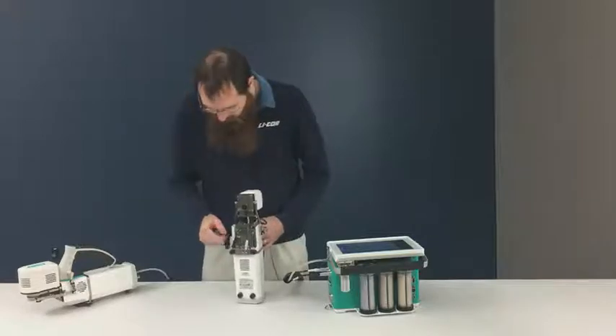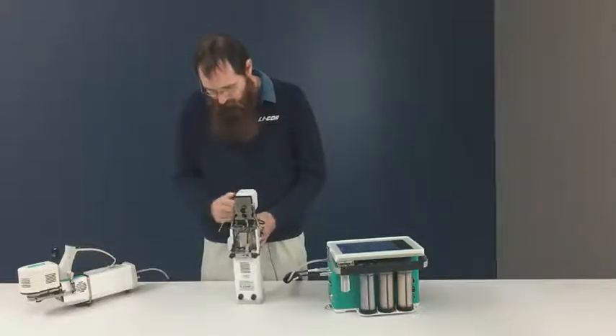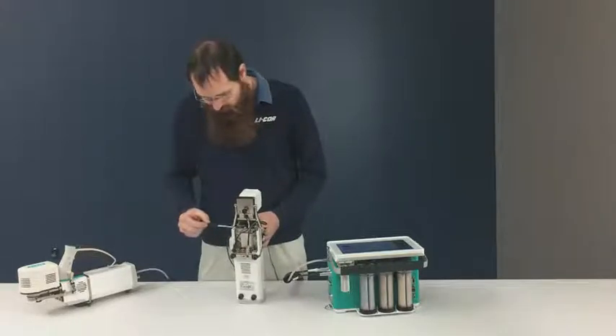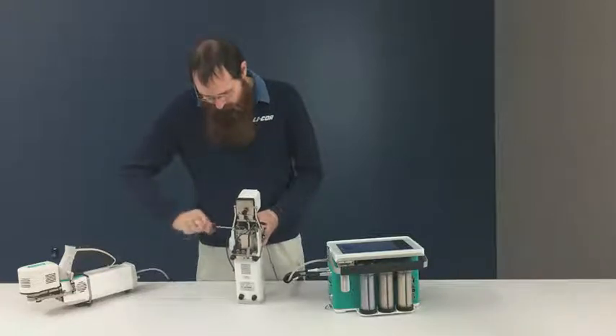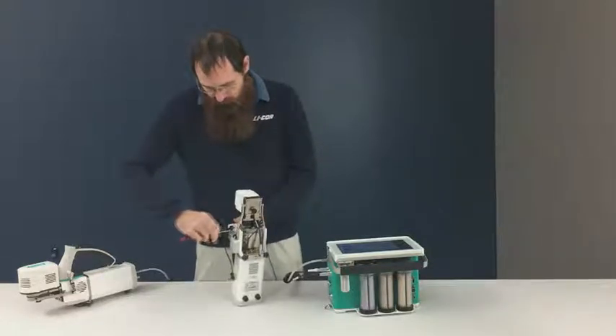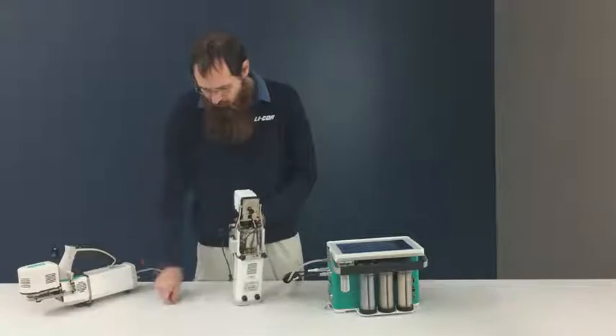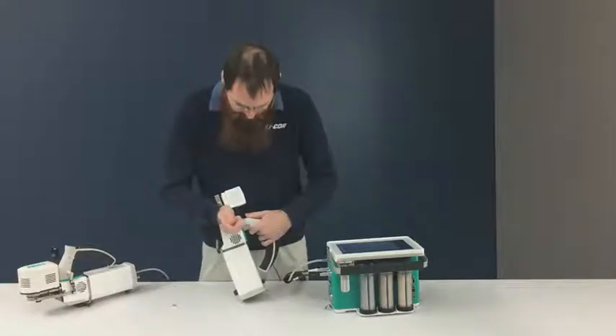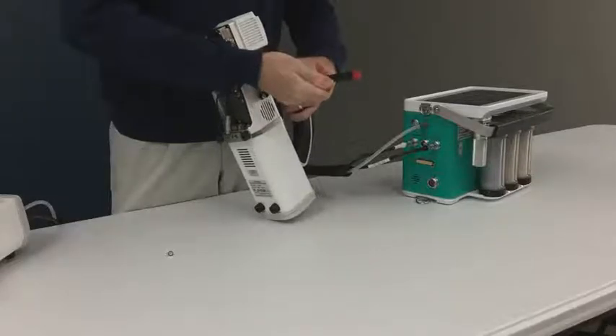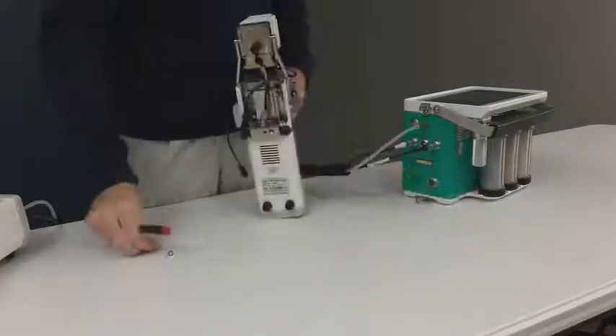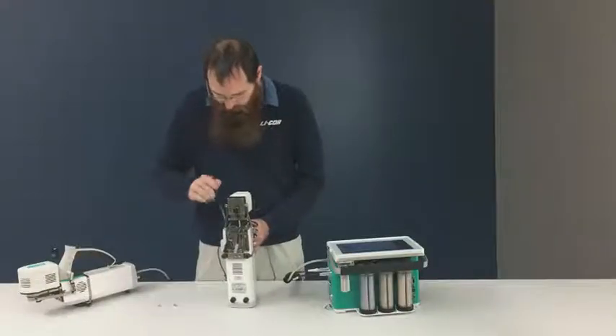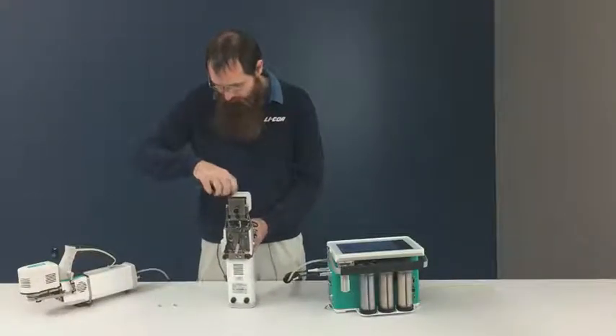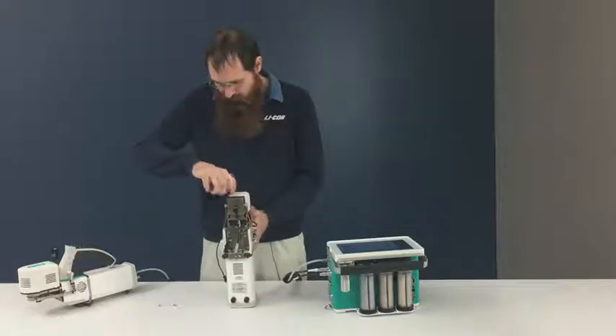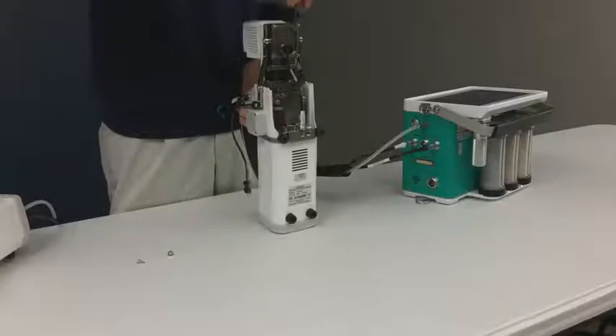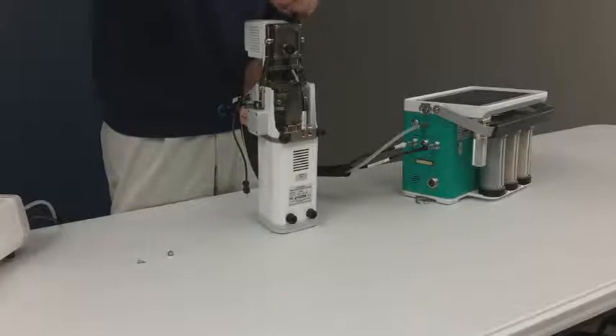If we disconnect those and pull this little cable out, I'll show you the back side of the chamber. We have to remove 4 screws to take a chamber off: the 2 that hold the springs onto the latch mechanism, and 2 captive screws in the base of the chamber.